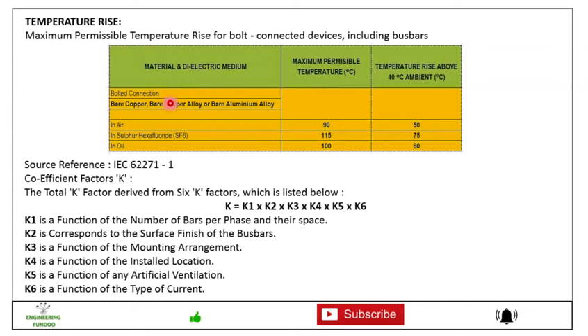Friends, then let's say for temperature rise, maximum permissible temperature rise for bolt connected devices including busbar. For material dielectric medium, for this bolted connection bare copper busbar or bare aluminum alloy busbar in air, maximum permissible temperature is 90 degree and temperature rise above 40 degree ambient permissible is 50. In oil 100, that means above 40 degree ambient it is 60 degree, and this is considered from the source reference IEC 62271 part 1.